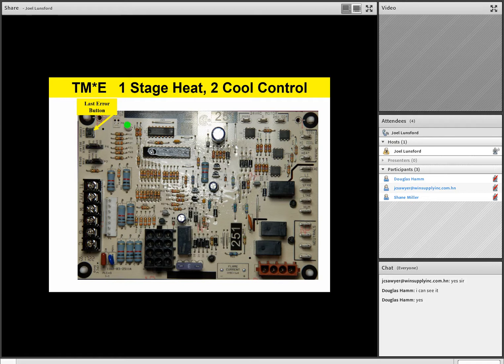Okay, as we move around the board, we have a status LED to retrieve diagnostic flash codes. And it should be noted that the diagnostic LED will flash either green, red, or yellow based on the flash code. Now as we move around the top of the board, you'll notice that there are some 24 volt motor terminals. You'll see one that says park. What that park means is that it's for an unused motor tap. So if you have like a 5-speed motor, but you're only using 2 or 3 of those speeds, you'll have a place to put that extra terminal. That's what they call a park terminal.